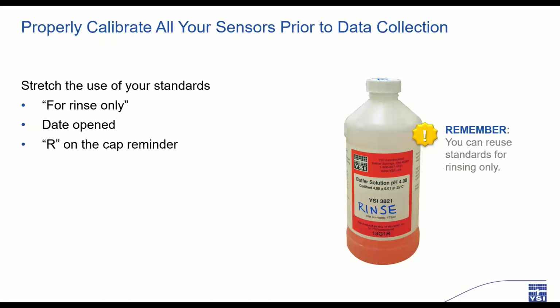Save the standard that you just used in a separate bottle, and then use a Sharpie to write on the bottle the day that you opened it. Then write "rinse only" on the label. And I also put the letter R on the cap, so that if I grab that bottle off the shelf and the rinse only note is turned away from me, I'm still likely to see that R on the top of the cap. This rinse only standard can be used the next time that you calibrate as a rinse of that parameter. This keeps me from having to use brand new pristine standards for the rinsing steps during calibration.